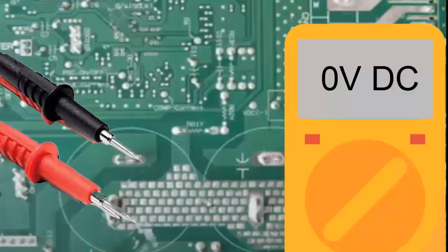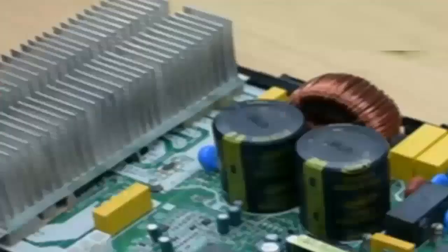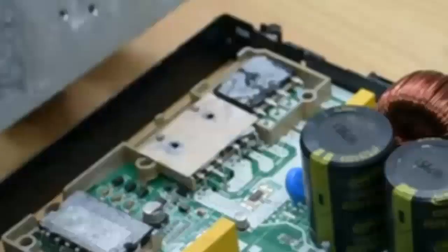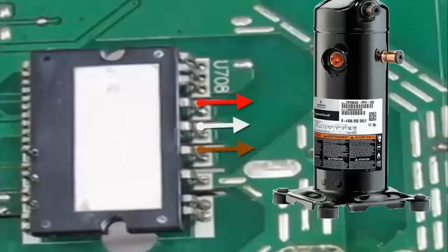Step 2: Locate the IPM electronic circuit. The IPM electronic circuit is covered by heat-dissipating fins. Its pins are connected via three independent tracks and an electrical connector to the three compressor pins.